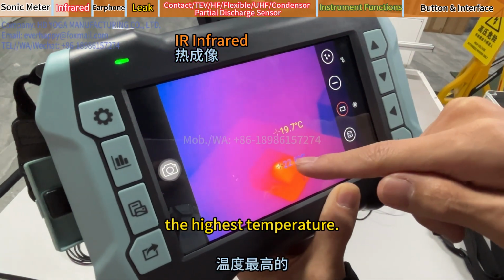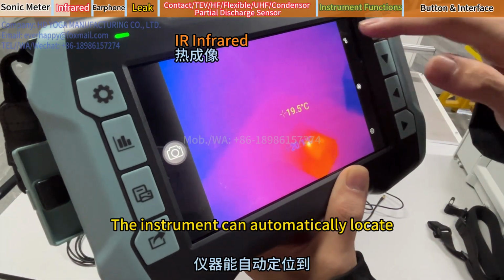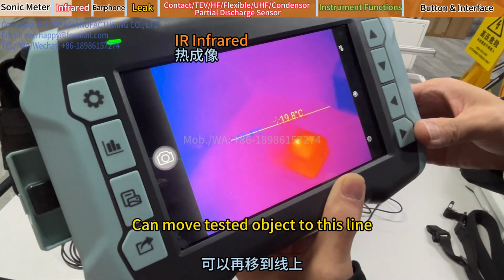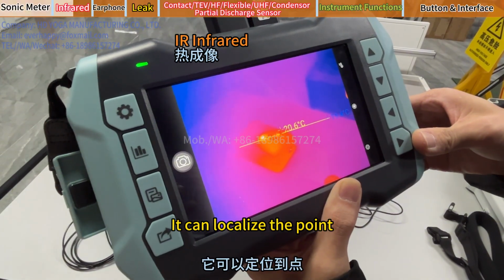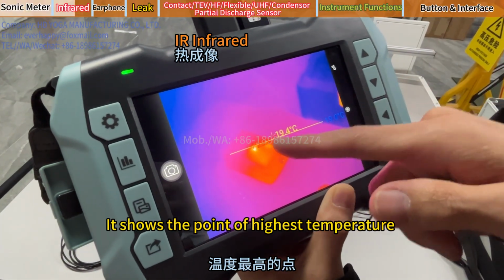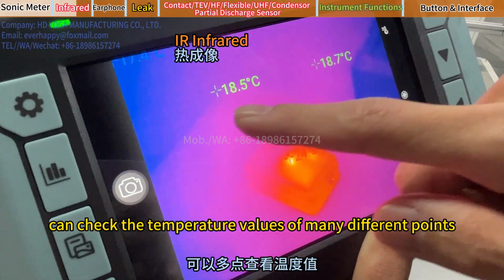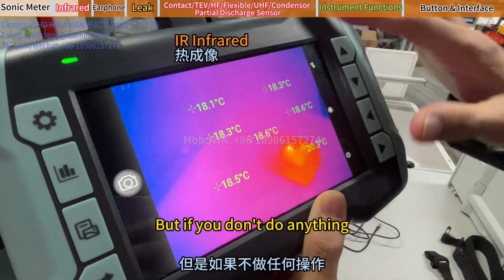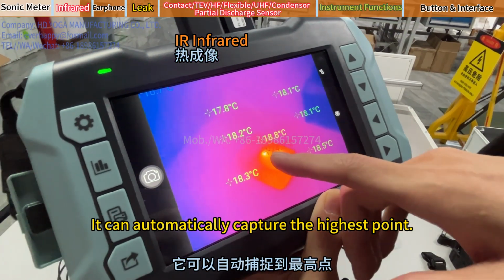It's the brightest, the highest temperature. The instrument can automatically locate. Line area, can move tested object to this line. It can localize the point. It shows the point of highest temperature. You can also draw a dot, can check the temperature values of many different points. But if you don't do anything, it can automatically capture the highest point.